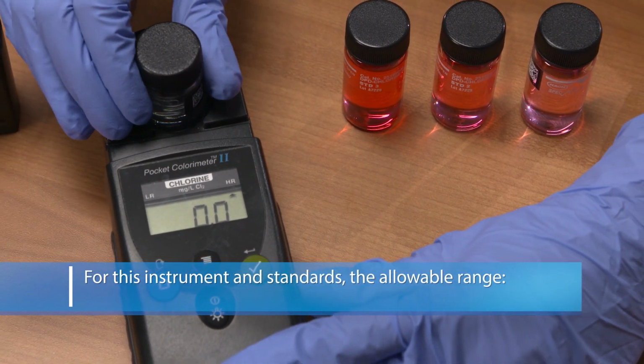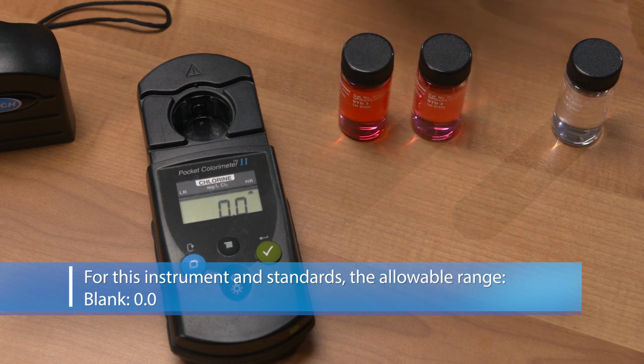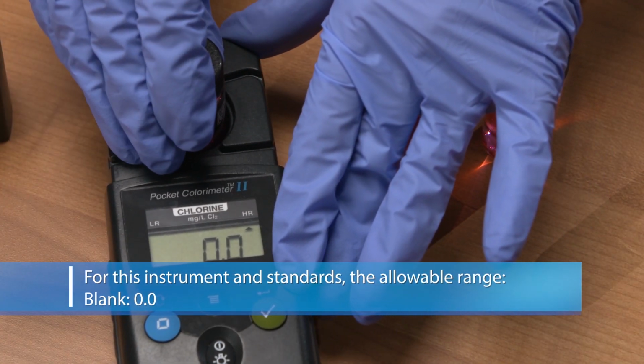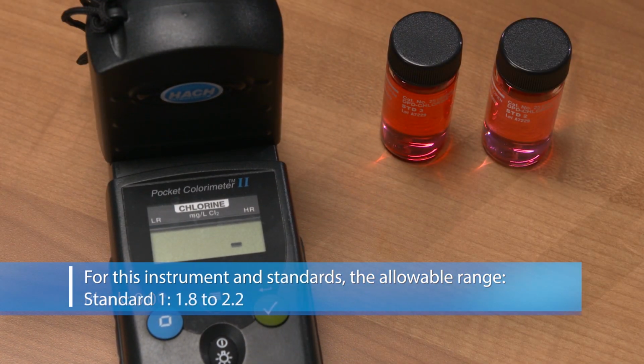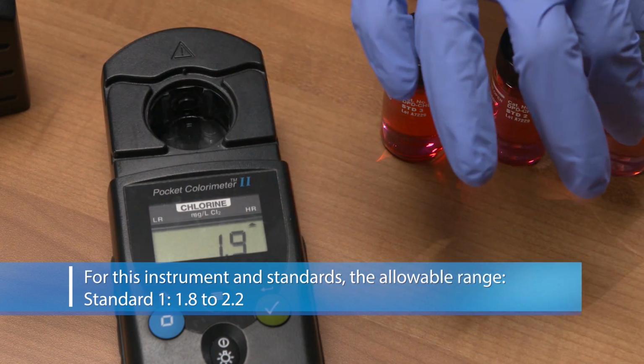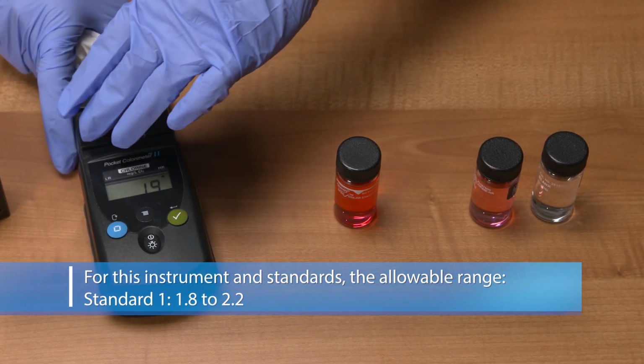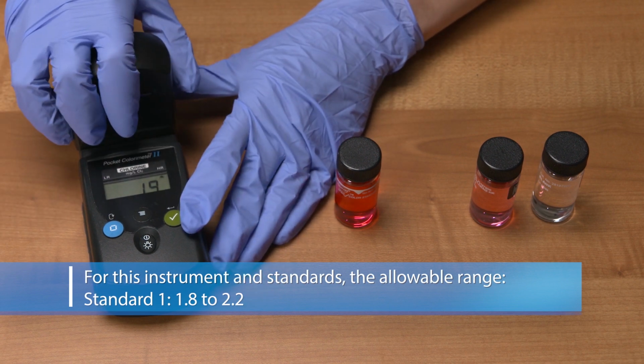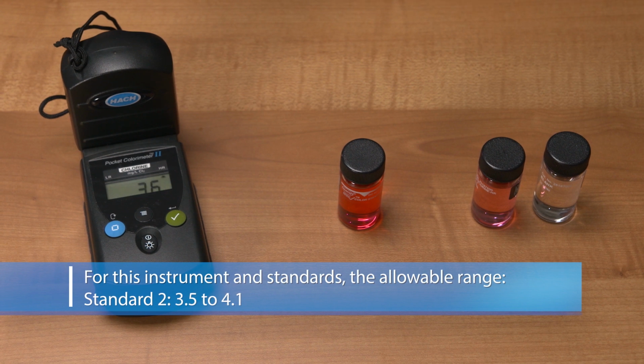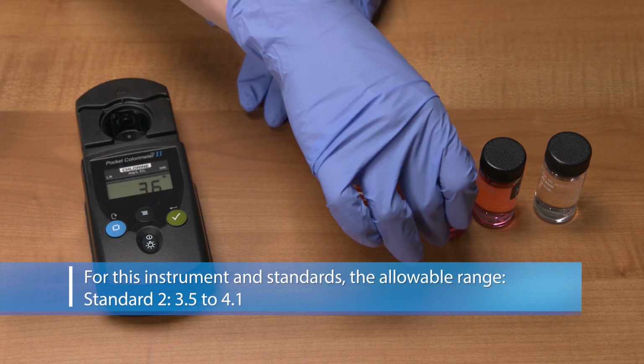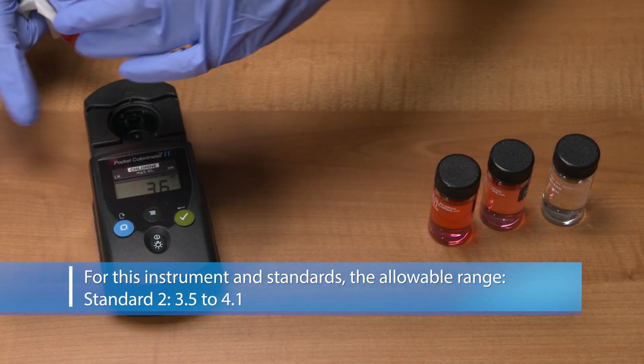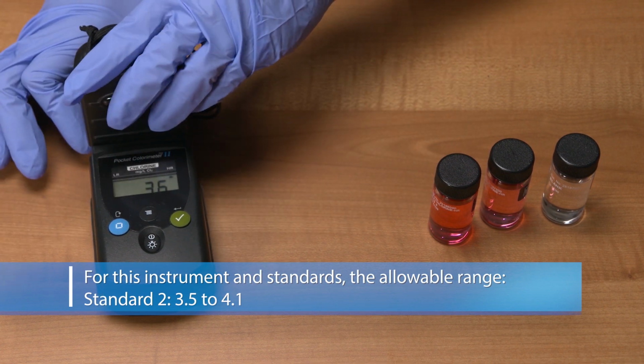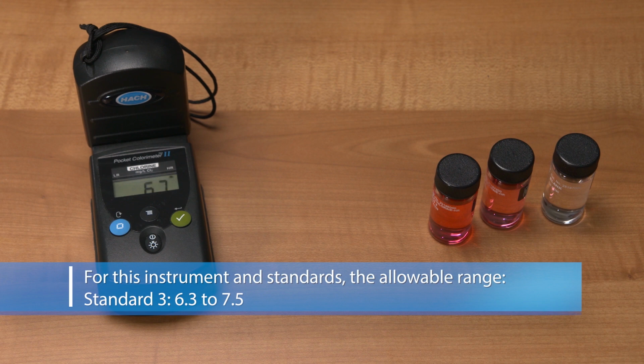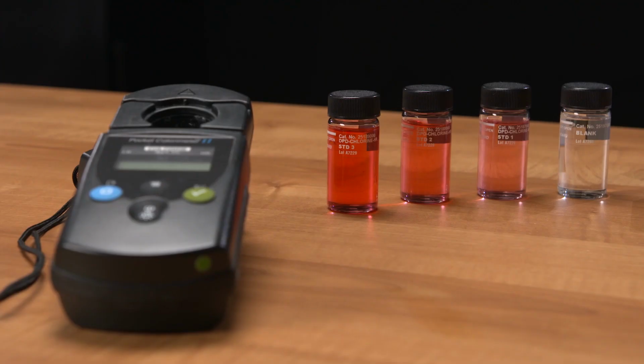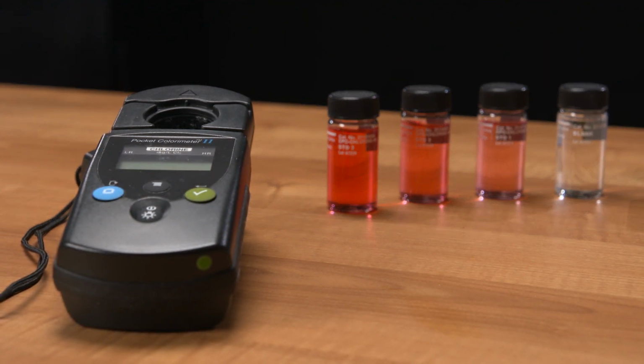For this instrument, the measurements are blank, 0.0, standard 1, 1.9, standard 2, 3.6, standard 3, 6.7. For this example, we have passed the secondary verification check because these measurements are in the allowable ranges.